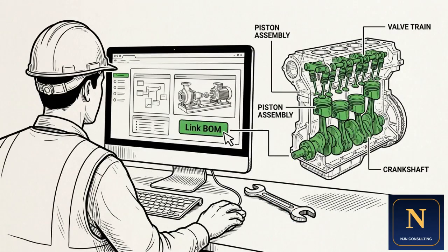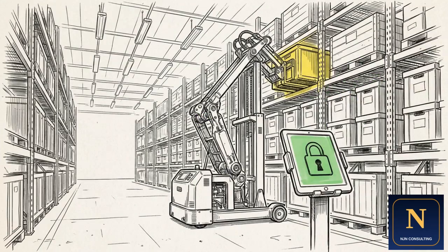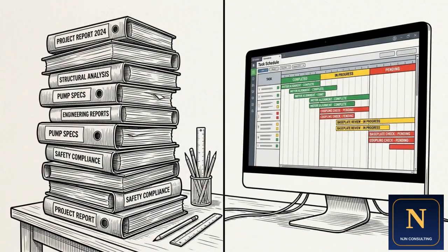The task list has to define exactly what the crew will do, how they will do it, the specific trade skills required, and the safety lockout state the machine must be in before work begins. By directly attaching the bill of materials to these task operations, the system automates the logistics. The exact spare parts are reserved in the warehouse the moment the work order is generated. The most rigorously researched maintenance tactic delivers zero value on paper. It only becomes real once it is hard-coded into the ERP system as an automated execution plan.